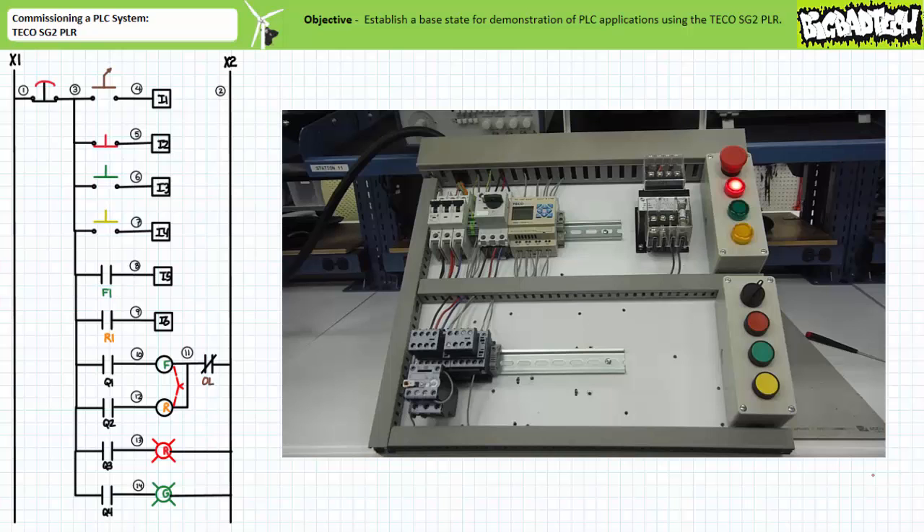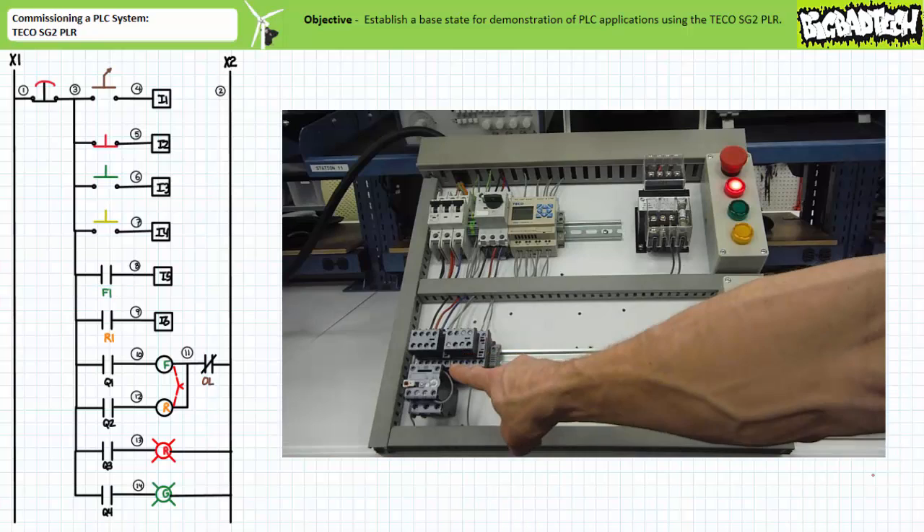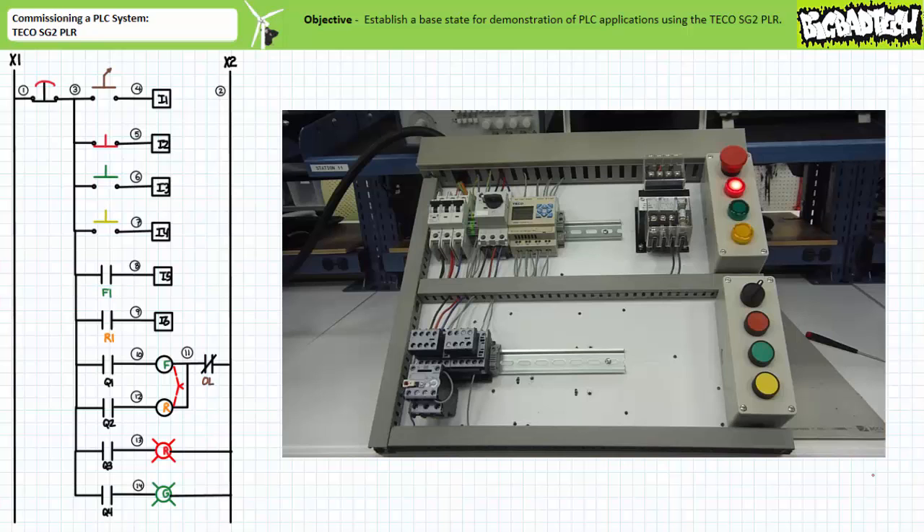Additionally, output Q3 remains energized and the red pilot lamp remains on. You note the F contactor carrier moves and the status screen should indicate that input I5 is asserted, meaning that the F contactor is closed.